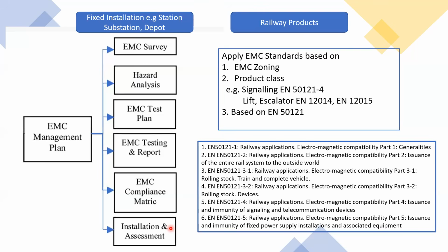So it is pretty possible to ensure the equipment meets requirements and is installed properly following the guidelines. There is also a requirement transferred to the operation and maintenance manual, where EMC requirements are taken care of if you change, repair, or reinstall equipment. The operation and maintenance manual will have recommendations on what needs to be done in terms of EMC.